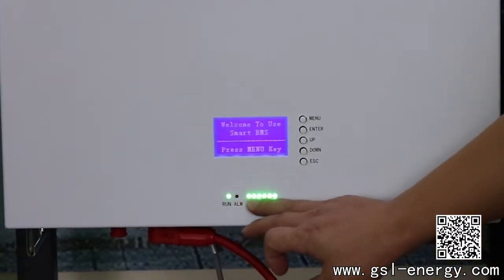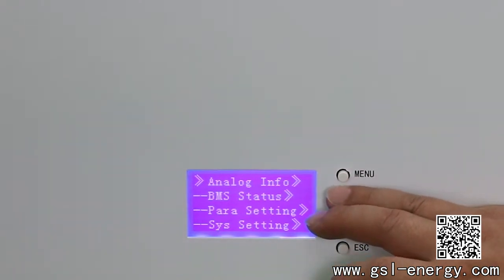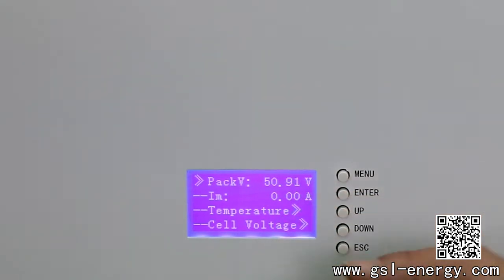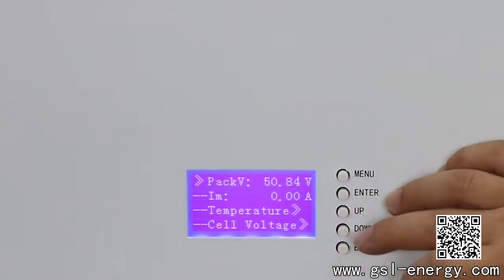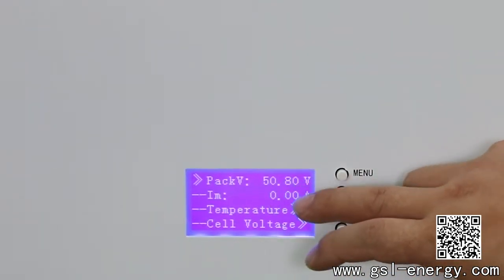For now, it shows the run lighting and capacity lights. On the BMS main screen, the information is displayed. Going into the entry group, the first one shows the pack voltage is 50.9V. The voltage configuration is 16S4P, so the total nominal voltage is 51.2V. For now it's not at full capacity, so it hasn't reached the peak voltage. Since there is no charge and no discharge at the moment, the current is zero.